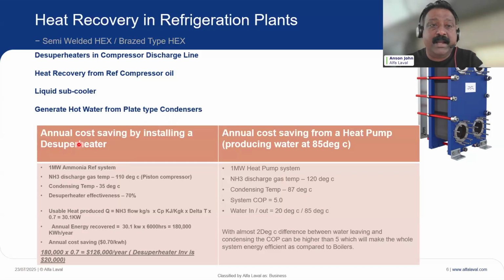So I have done a cost saving analysis by adding a de-superheater. Suppose you've got a 1 megawatt ammonia refrigeration system, which will have an ammonia flow rate of around 0.23 kg per second, and you've got a piston compressor at the site, which generally has a discharge gas temperature of around 110 degrees C, and it can go up to 150.